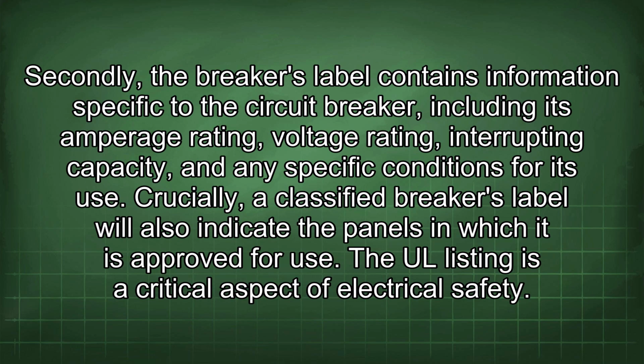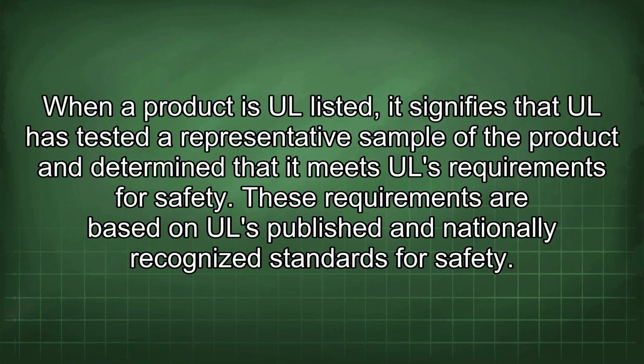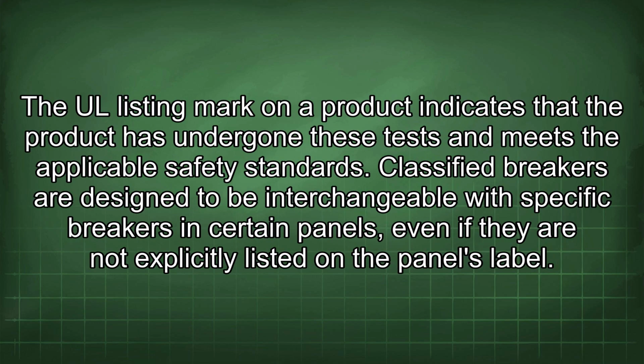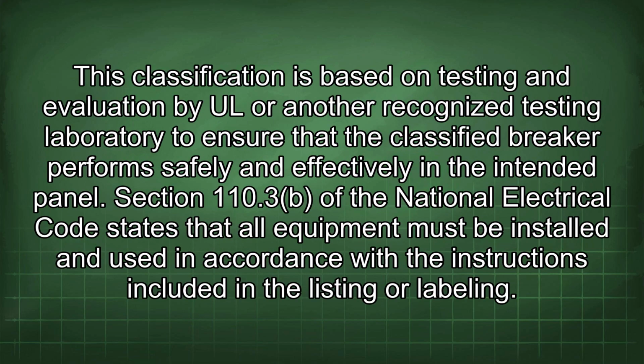The UL listing is a critical aspect of electrical safety. When a product is UL listed, it signifies that UL has tested a representative sample of the product and determined that it meets UL requirements for safety. These requirements are based on UL published and nationally recognized standards for safety. The UL listing mark on a product indicates that the product has undergone these tests and meets the applicable safety standards. Classified breakers are designed to be interchangeable with specific breakers in certain panels, even if they are not explicitly listed on the panel's label. This classification is based on testing and evaluation by UL or another recognized testing laboratory to ensure that the classified breaker performs safely and effectively in the intended panel.